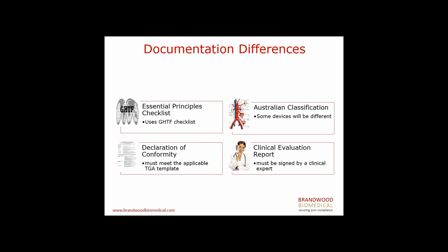be signed by a clinical expert. The clinical expert here, we've had a few questions and confusions about this. A lot of people ask, does it have to be a surgeon or does it have to be a clinician? And the answer to that really is maybe. There are two key factors to take into account, and that is the qualification of the person. Are they qualified appropriately to the device and where it's used, and also their experience. Are they using the device, or are they qualified and have the experience to know how a device works and whether it'll be safe and perform as intended?